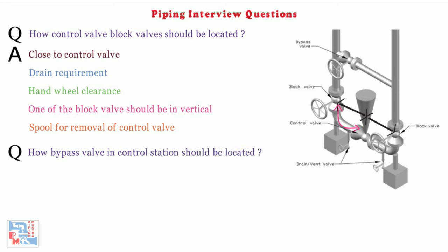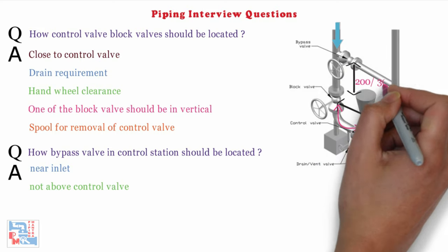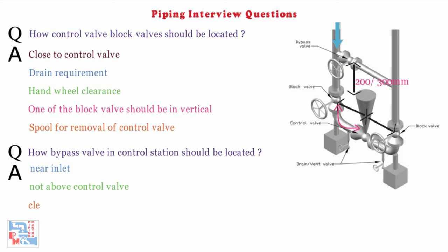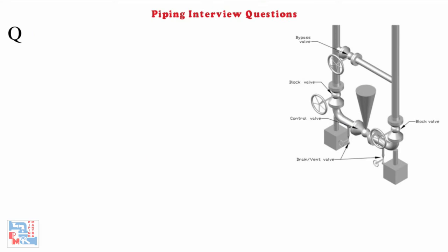Next: how should the bypass valve in a control station be located? The bypass valve should be near the inlet branch point, preferably not above the control valve. It should have a minimum 200 to 300mm clearance between the actuator and valve for removal of the control valve during maintenance.